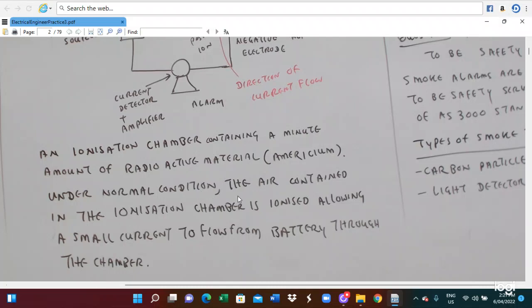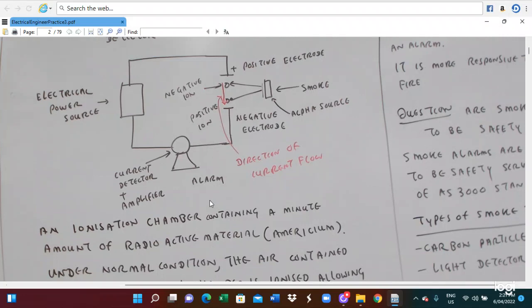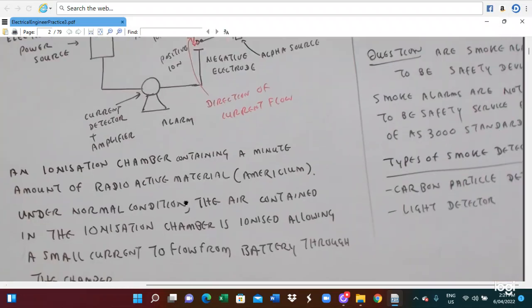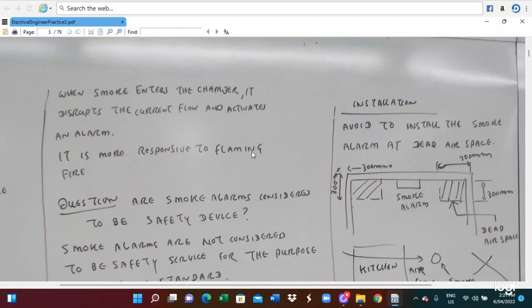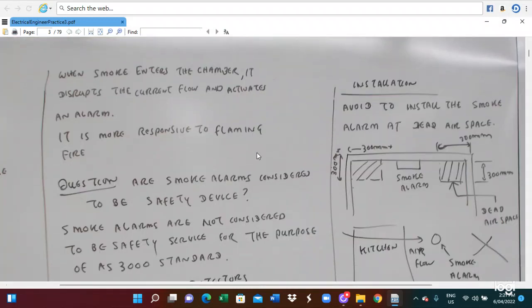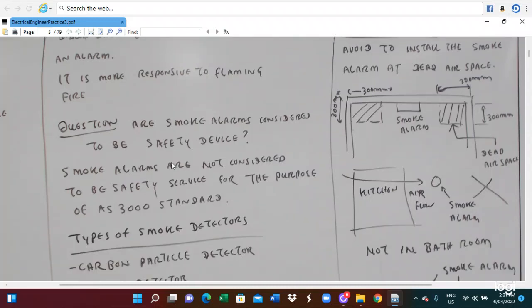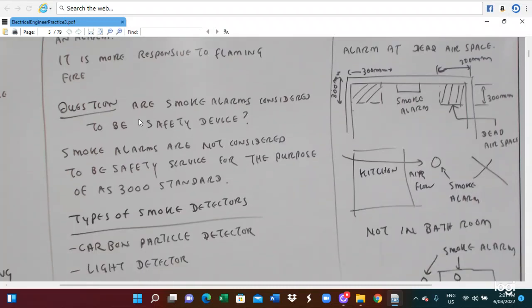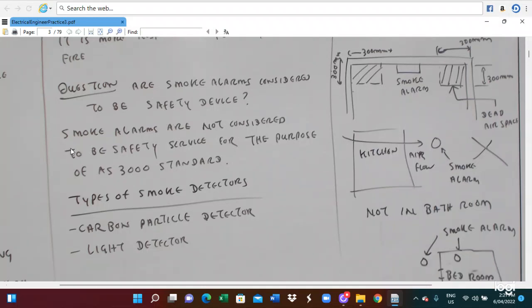Under normal conditions, the air in the ionizing chamber is ionized, allowing a small current to flow from the battery through the chamber. When smoke enters the chamber, it disrupts the current flow and activates the alarm. It is more responsive to flaming fire. Smoke alarms are not considered to be safety devices for the purpose of the AS3000 standards.